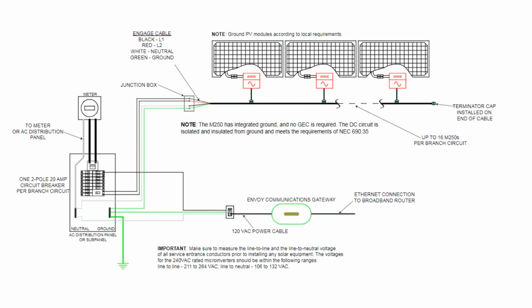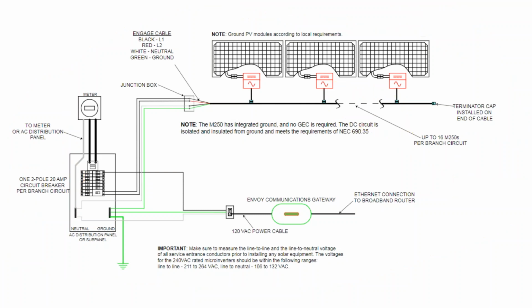It used to be we would draw these out in a drawing program, whether CAD or something cheaper. This one wouldn't be too hard to create yourself, because Enphase limits their circuits to 20 amp breakers, and there are up to 16 panels, so you could take this CAD file and change it to specify how many panels are on that circuit, giving you a wiring diagram for a one-circuit solar array good enough for some jurisdictions. You could then ask your electrician what size wire to use on 20 amp wiring, and they'd probably get it right since it's just AC. You can do Romex through the attic with microinverters.